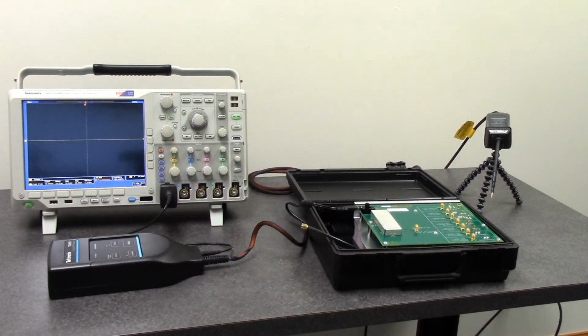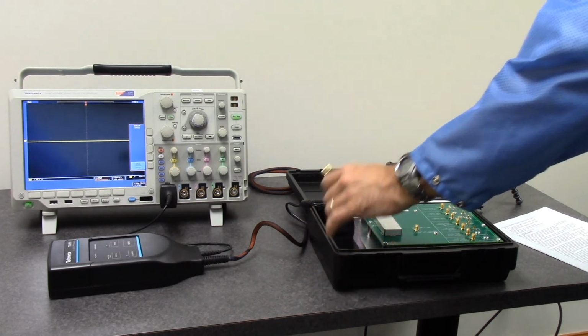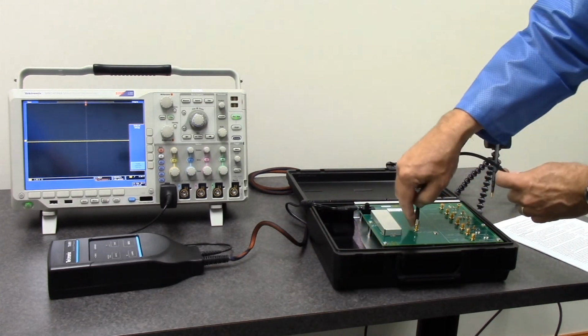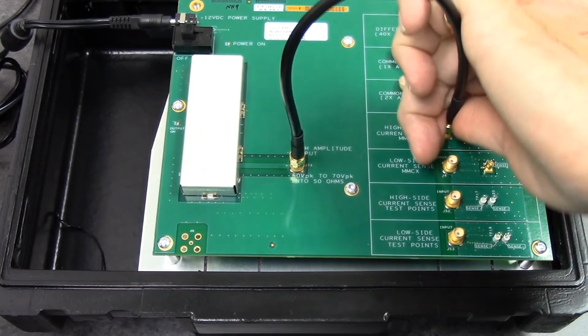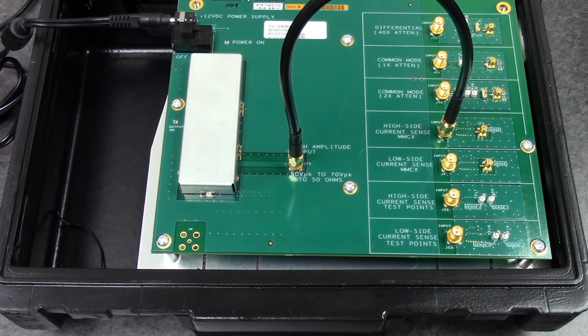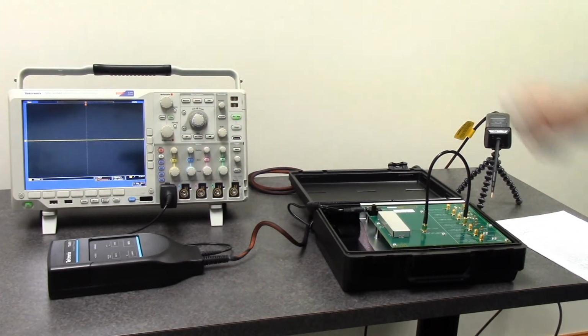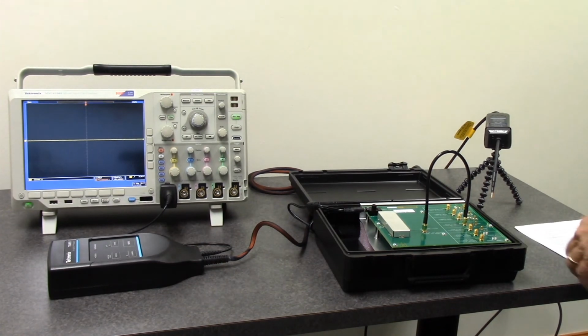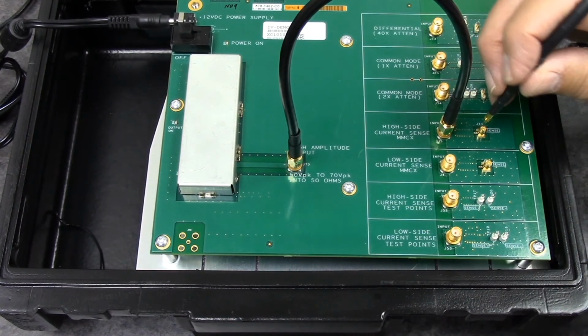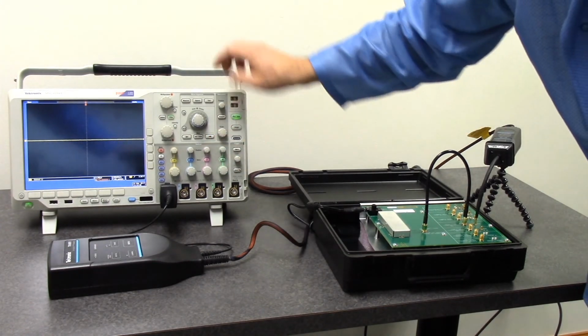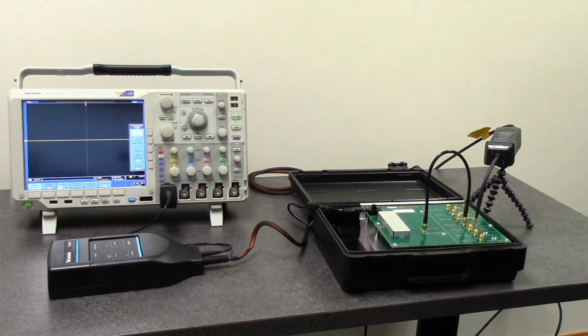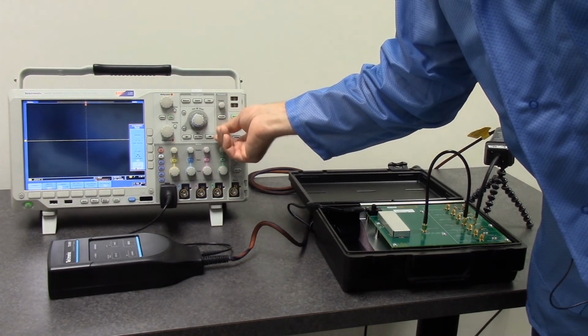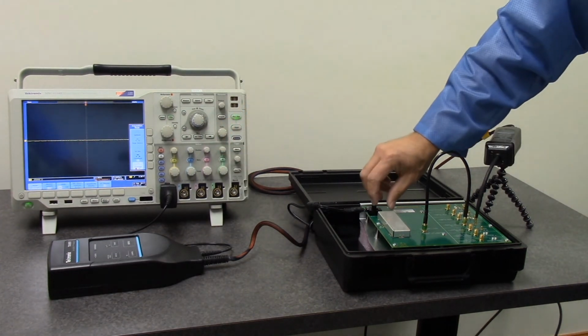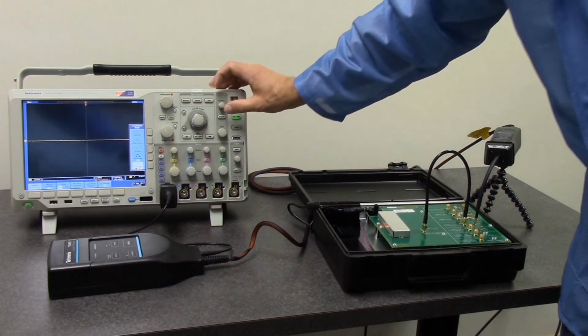For this section, we will once again follow the procedures included in the lab guide. Now connect the SMA cable from the high amplitude output to the high side current sense MMCX SMA connector J5. The IsoVu is connected to channel 1 of the scope. We'll connect the probe cable to the MMCX connector on the high side current sense MMCX section of the demo board. Set the scope to averaging, set the vertical scale to 250 millivolts per division and the horizontal scale to 4 nanoseconds per division. Now we'll power on the demo board and adjust the trigger level.